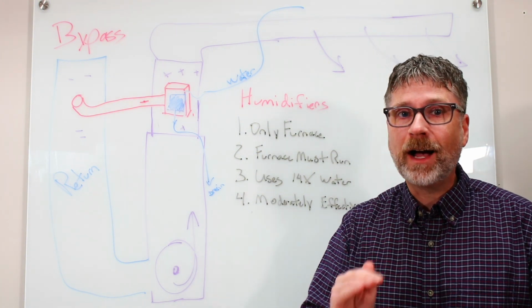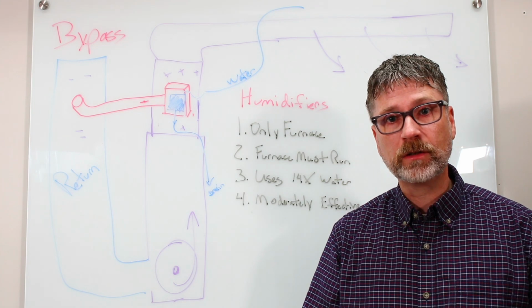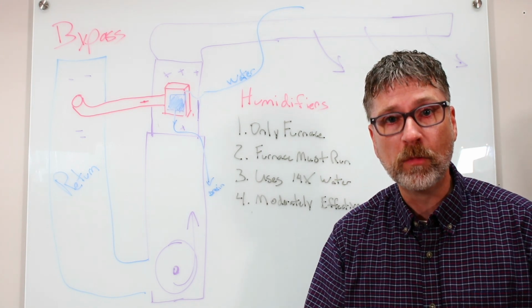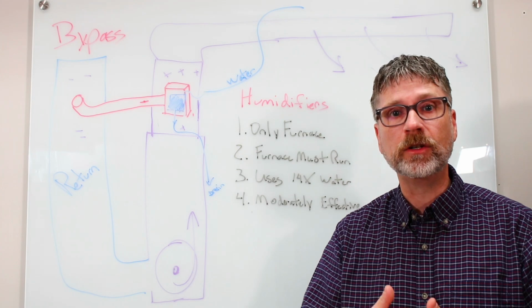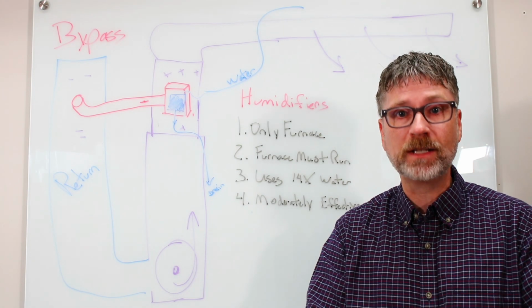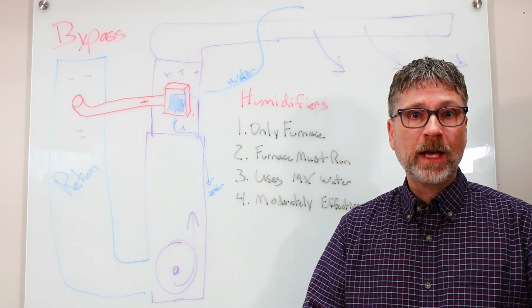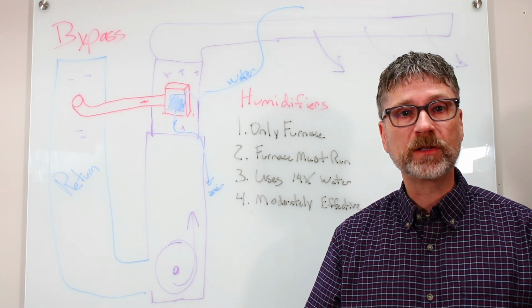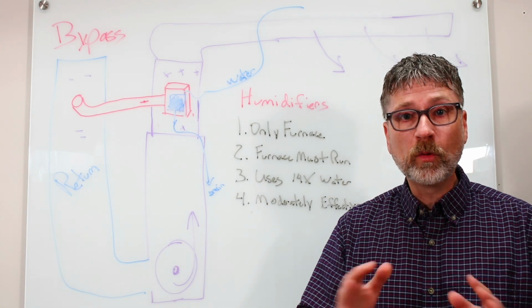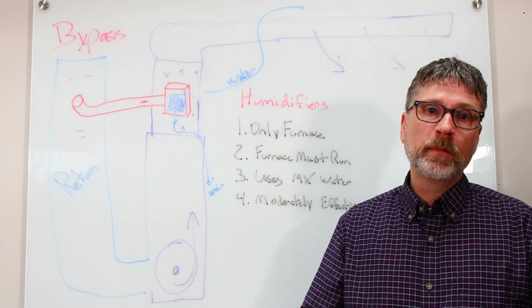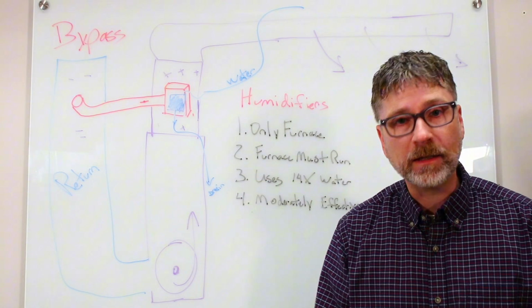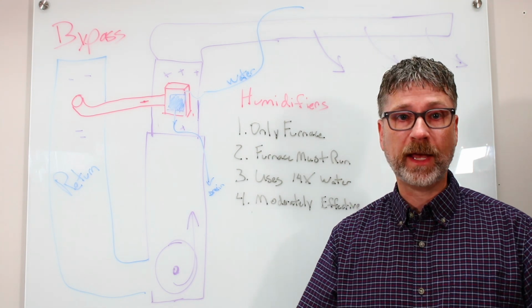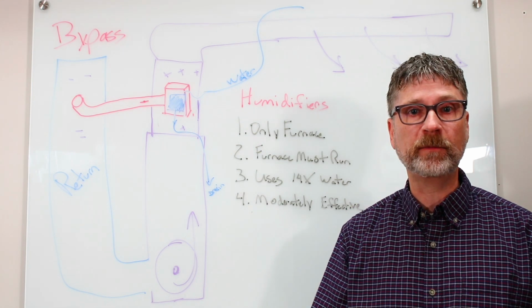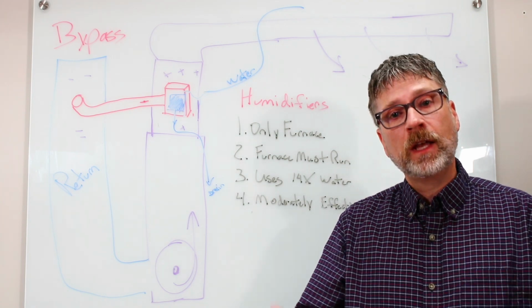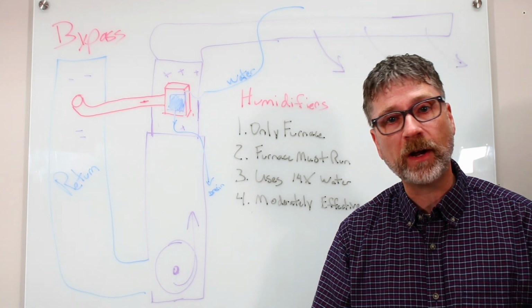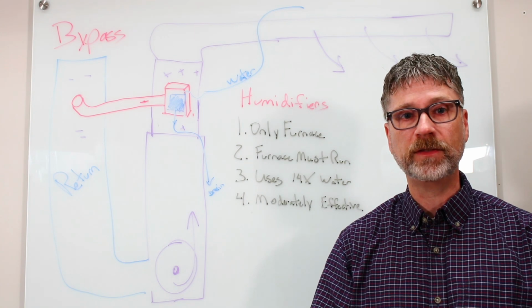Next, as this option relies on evaporation across the panel, it uses much more water than it puts into your air, as much as 14 times more water. And at the end of the day, a bypass humidifier is only moderately effective. It will raise your humidity levels some, but you may not reach your target. For maintenance, a bypass humidifier requires annual replacement of the evaporative pad, which is an inexpensive part. And installed, the cost of a bypass humidifier is usually around $750.